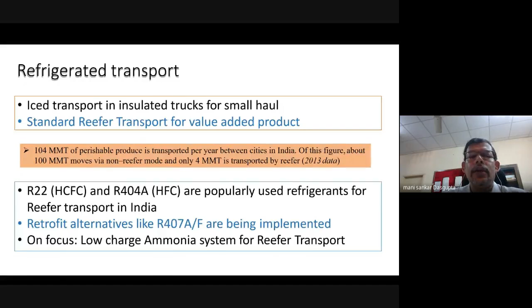Even where refrigerated transport is used, we generally still use R22, which has been banned in many European countries, and R404A, which is generally used in India. Retrofittable alternatives are available, meaning you don't need a lot of technical or component changes in the refrigeration circuitry, but can directly use R407A or similar, which is being implemented. However, the focus is on low charge ammonia systems for refrigerated transport, and also using other natural refrigerants such as CO2.